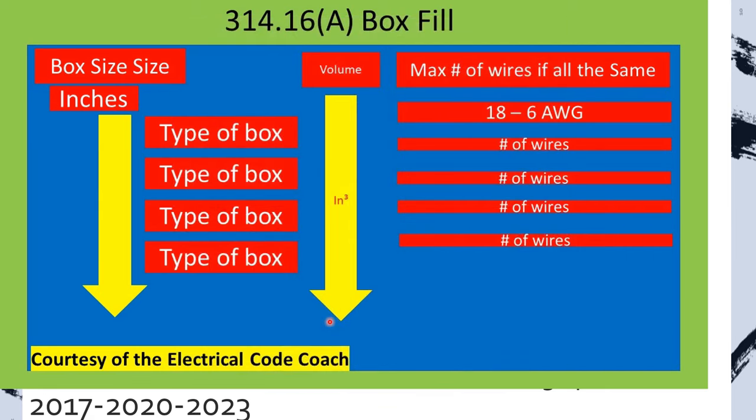The next column that we need to pay attention to is this middle one right here. Now, in the NEC, it actually says a minimum volume, which is kind of deceptive to the installer because it's actually your maximum volume that you're allowed to fill that box. And it's listed in cubic inches.